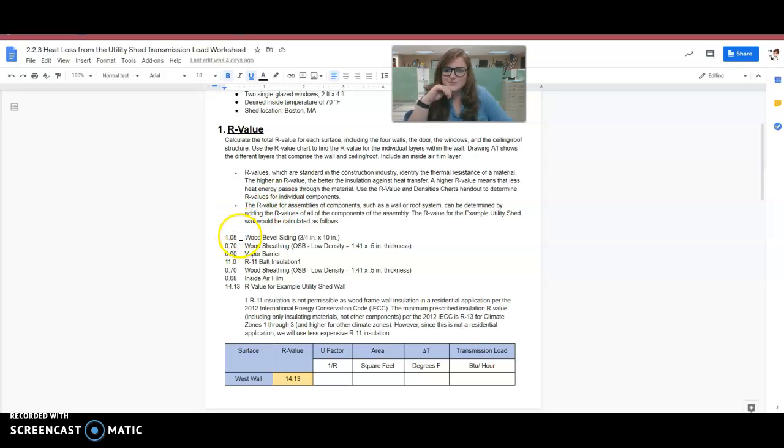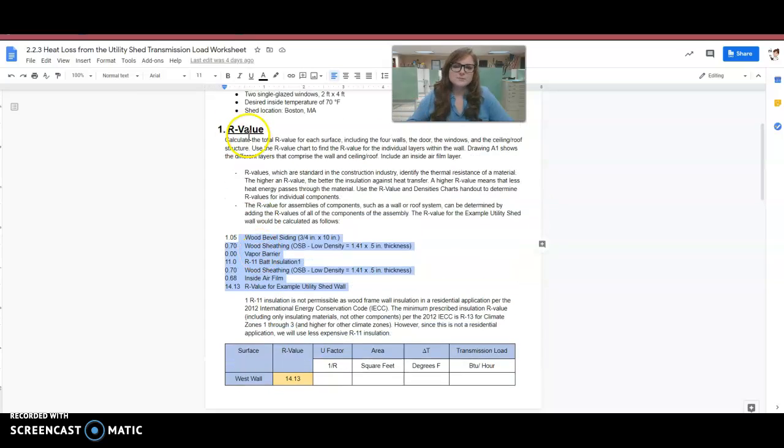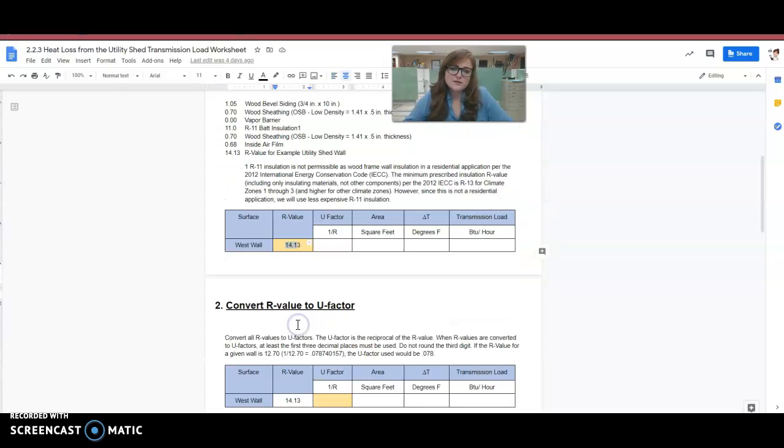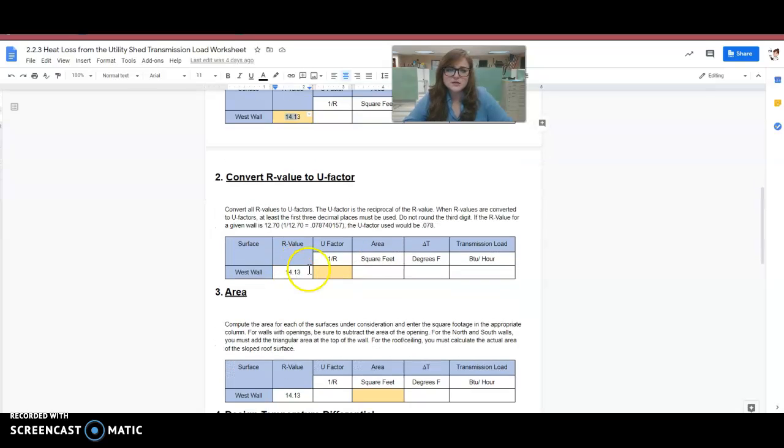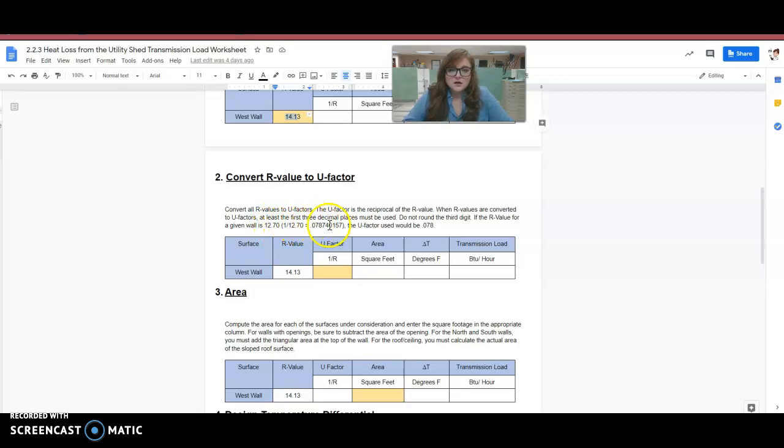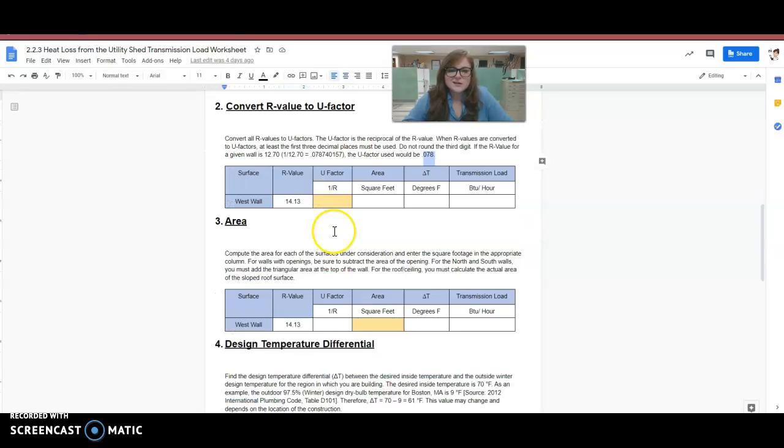So it talks about all of the different layers of that wall. And the first step is to calculate the R value. So we get the R value. Now we have to go and calculate the U factor. So convert all R values to U factors. And again, in the PowerPoint it goes over how to do this. Do not round to the third digit. If the R value for a given wall is 12.70, the U factor should be used as 0.078.